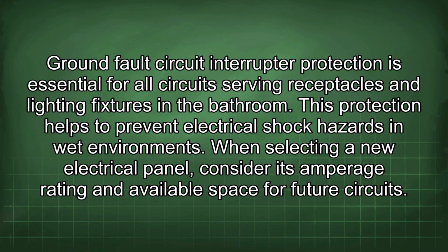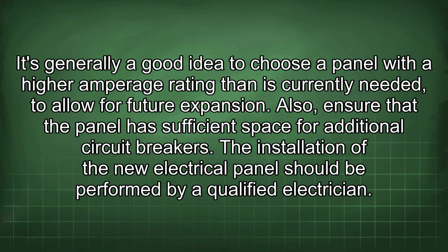When selecting a new electrical panel, consider its amperage rating and available space for future circuits. It's generally a good idea to choose a panel with a higher amperage rating than is currently needed to allow for future expansion. Also, ensure that the panel has sufficient space for additional circuit breakers.